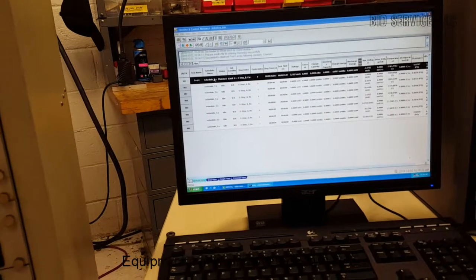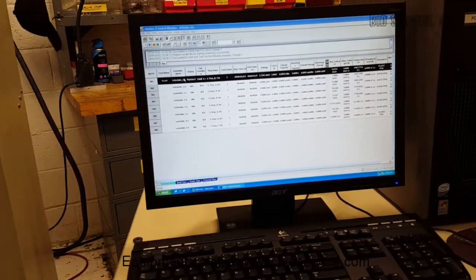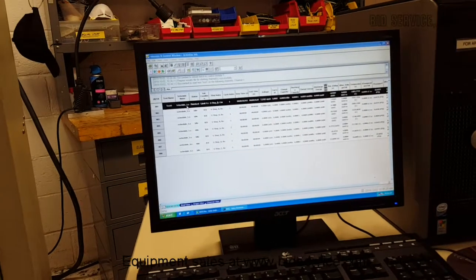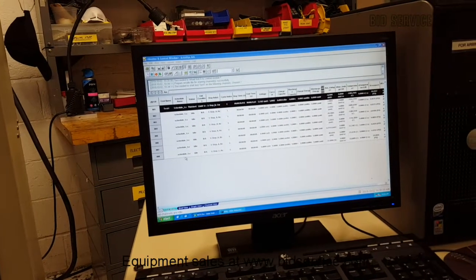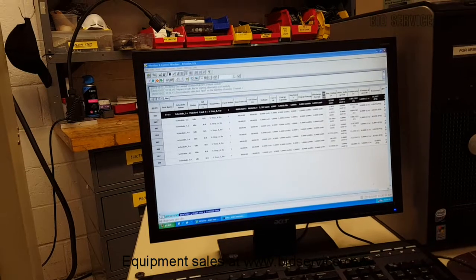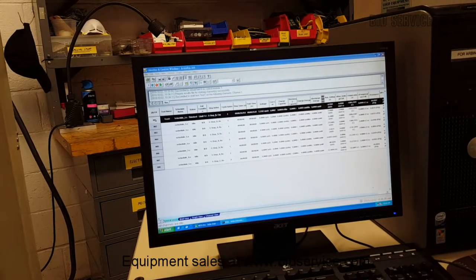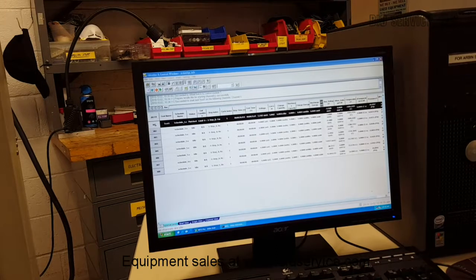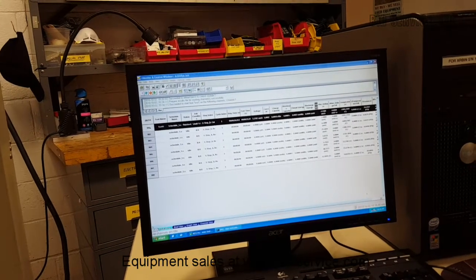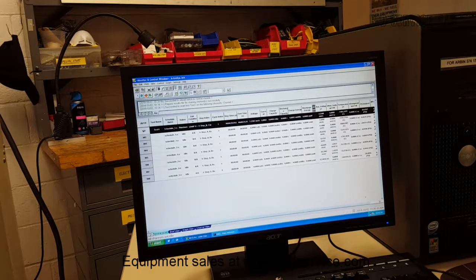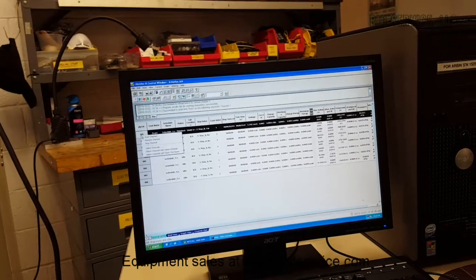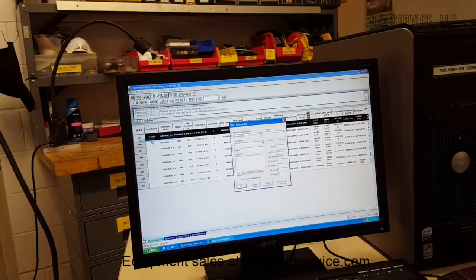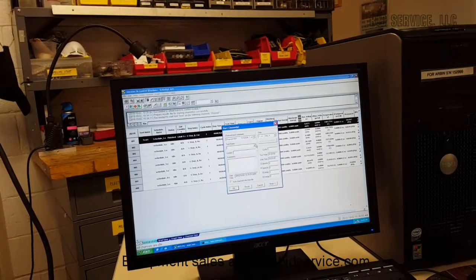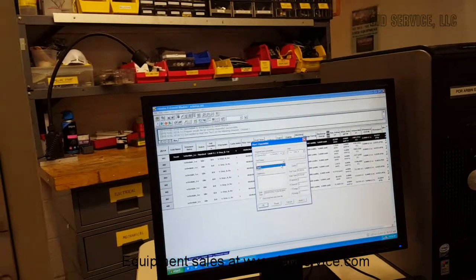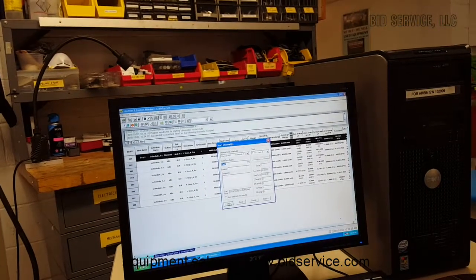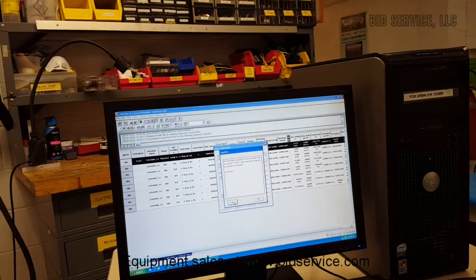So we've run that first test. Now what I'm going to do is run a current test on all the channels at one time. That one we just did, we're going to do again, and this is the other way you can start the channels as well. You left click on the channel, then right click, and it'll say start channel. It'll do the same thing as the running man icon at the top of the screen. Test 1, and here we go.